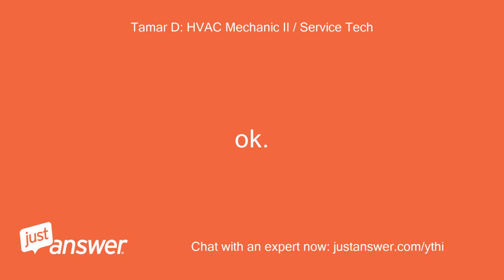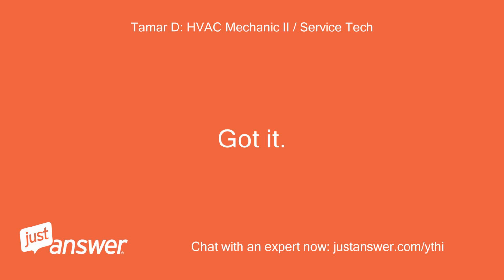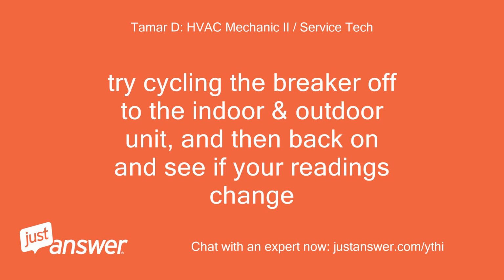Okay, I got it. On the 12 VDC part, did you have 12 volts DC going out? No, nothing on the DC side. Got it. So 24 V AC into the hub, but the hub isn't sending 12 VDC to the thermostat. That sounds like a hub issue. Try cycling the breaker off to the indoor and outdoor unit, and then back on and see if your readings change.